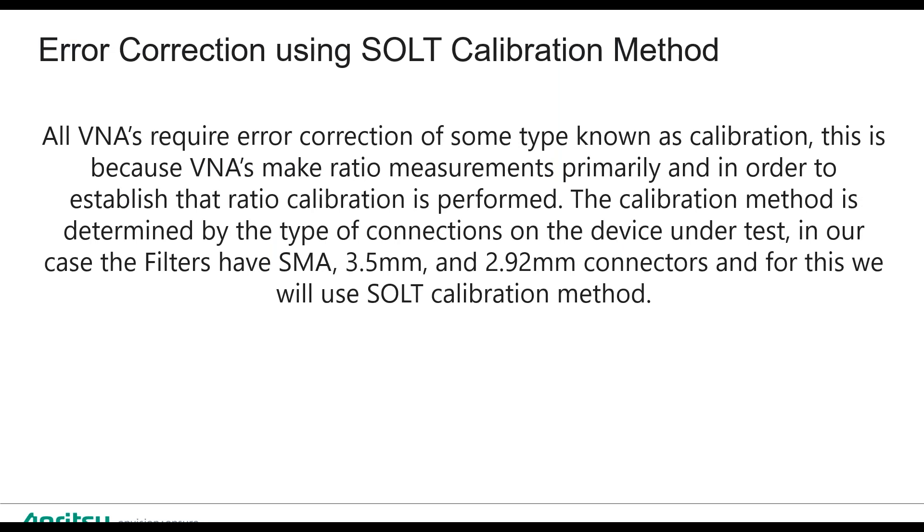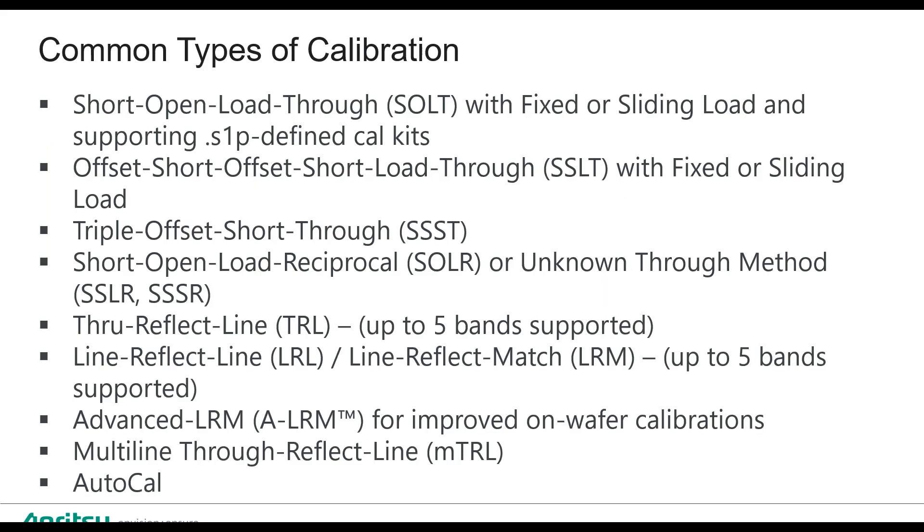Once we set the parameters for the VNA, we have to apply error correction or calibration. In today's case, the devices we're going to measure are SMA 3.5 millimeter, 2.92 millimeter, so we'll be using a 3652A mechanical calibration kit. But you should know that when you perform calibration, that's going to be determined by the DUT or device under test.